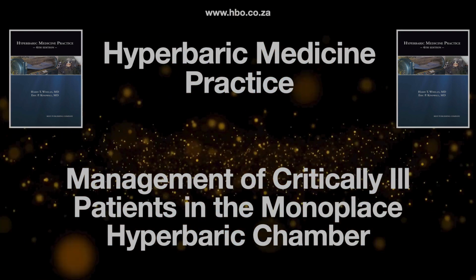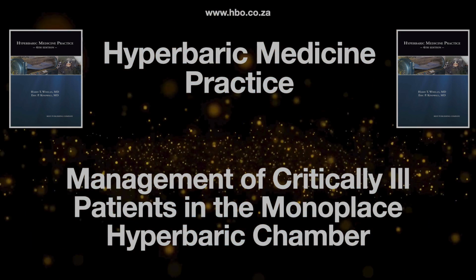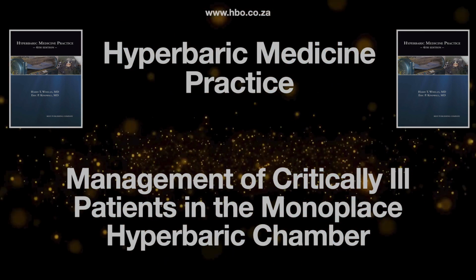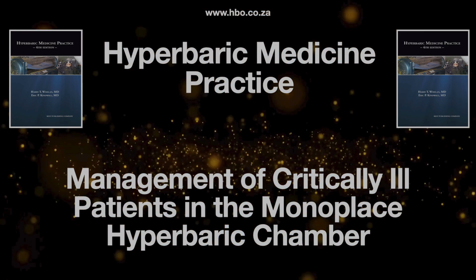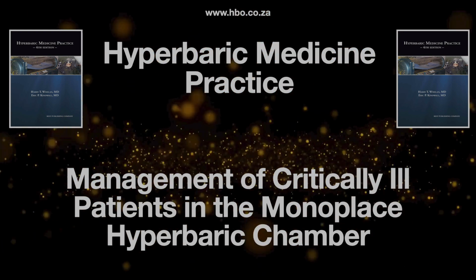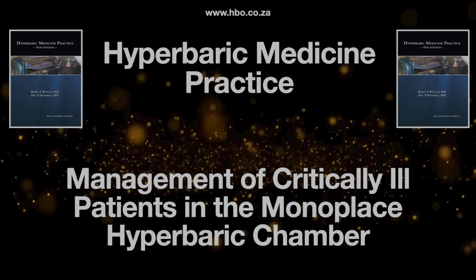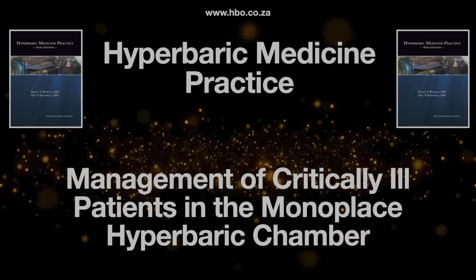What ventilators are actually used in the U.S. for monoplace chambers? The Sechrist 500A is the historical workhorse. Yeah. Pneumatic, time-cycled, controls outside. You set flow, inspiratory time, expiratory time. Tidal volume comes from flow and inspiratory time. Rate from expiratory time. Oxygen comes in through a pass-through. PEEP is added with external valves.